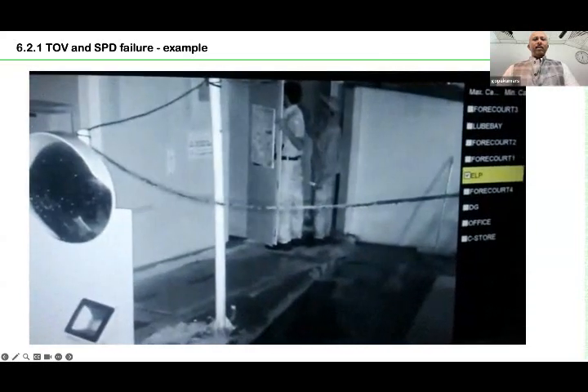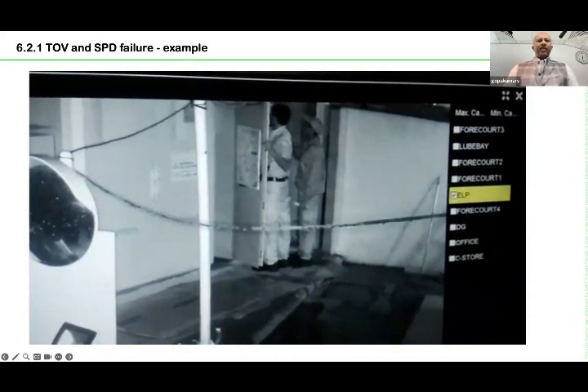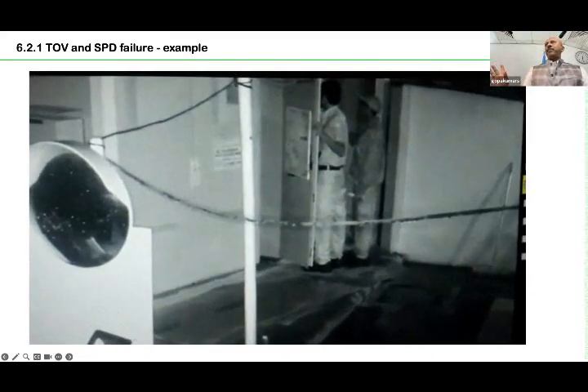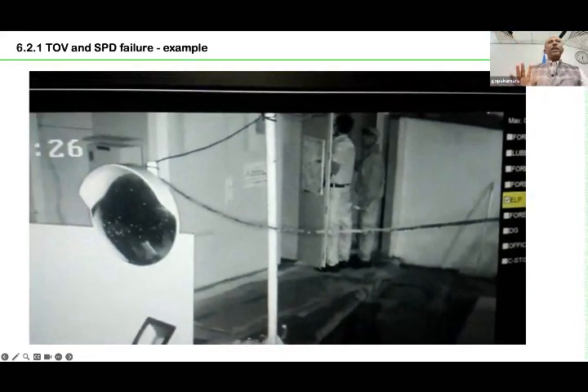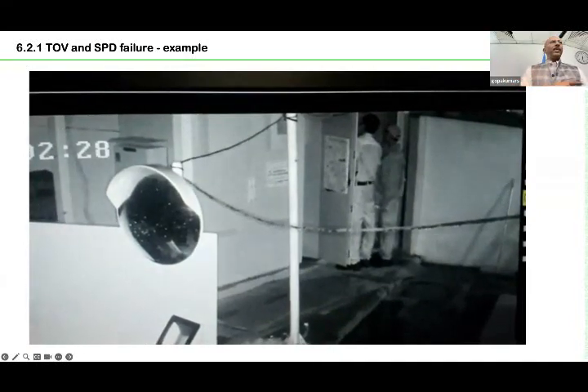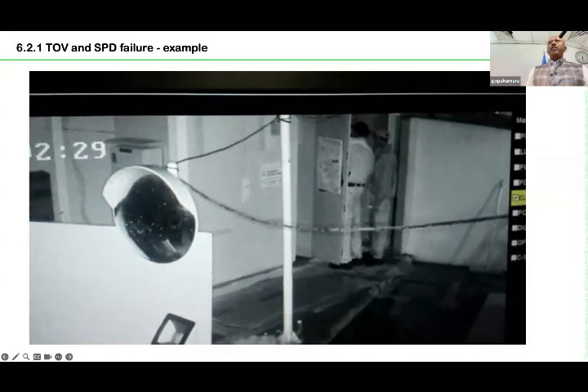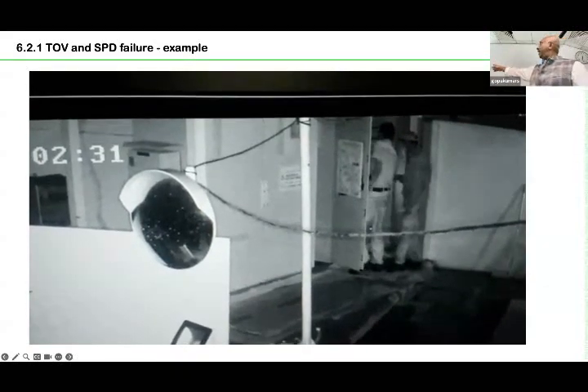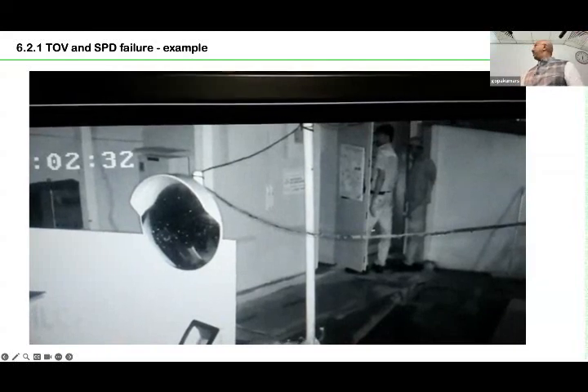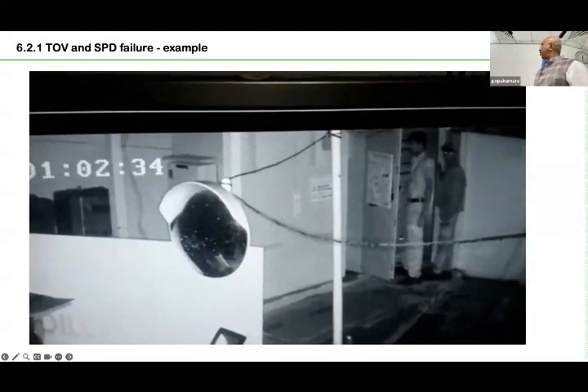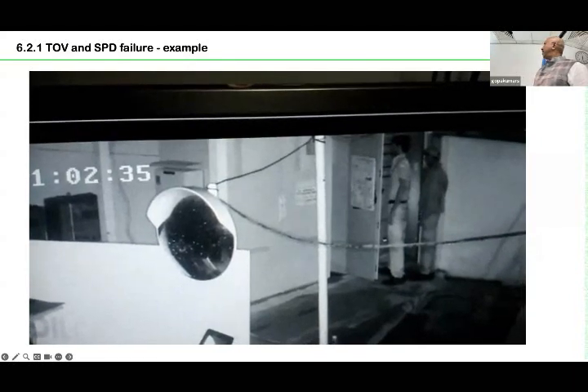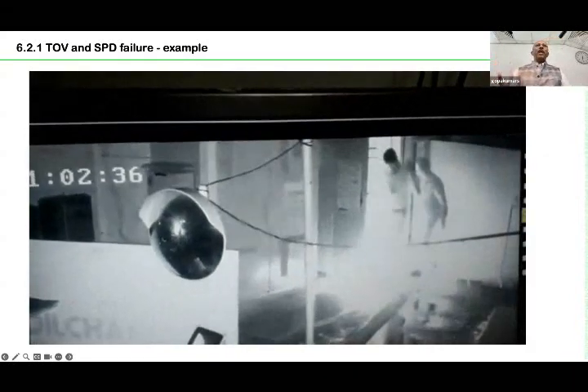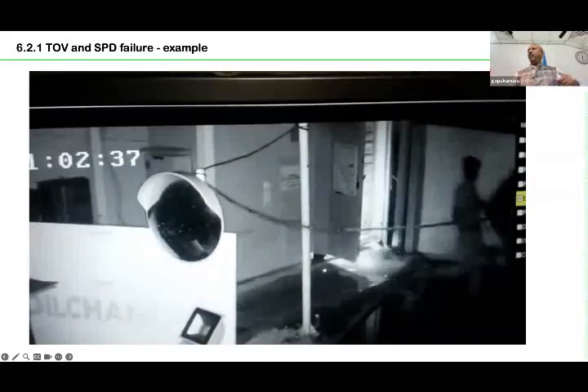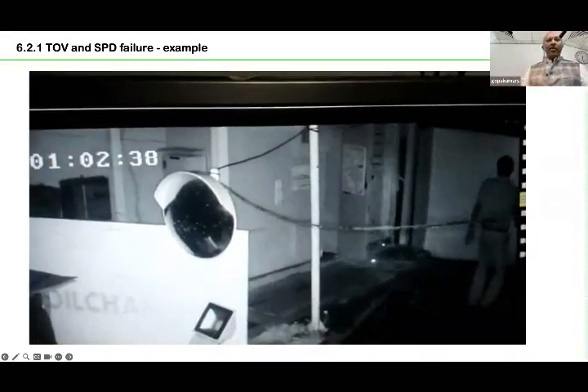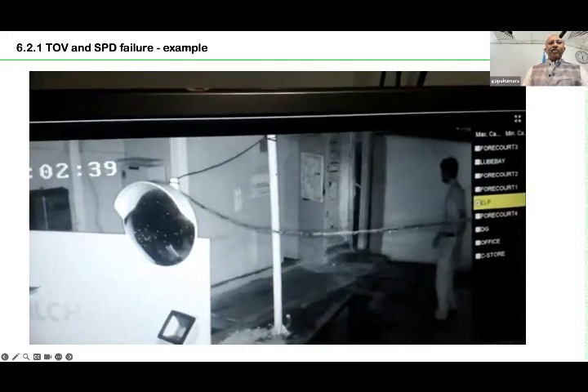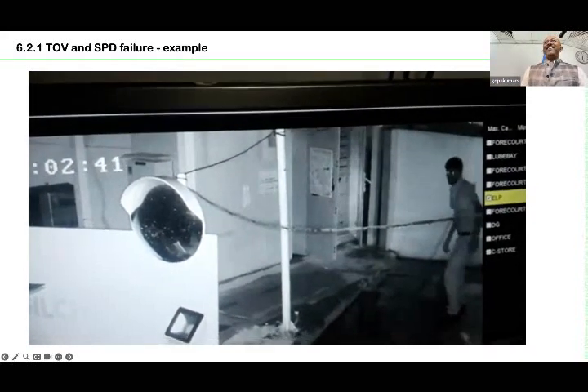You see, this is in a petrol pump. The previous day, the incoming breaker tripped due to some reason. So without checking the reason, they went and switched on the breaker. So this guy is standing there and he is telling the other fellow, okay, you switch on. So he is looking at it and he said to switch on. Yeah. So the SPD blasted because there was neutral isolation and the voltage was high. The SPD blasted. Luckily, nothing happened to them. You see, courageous fellows, they ran away. And it's a petrol pump. Would be nice.